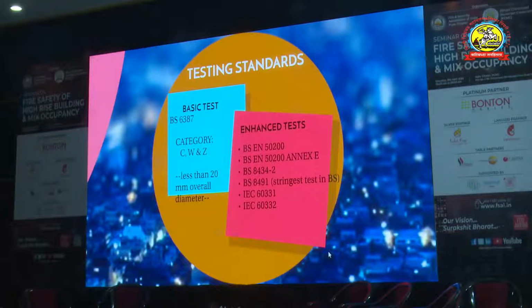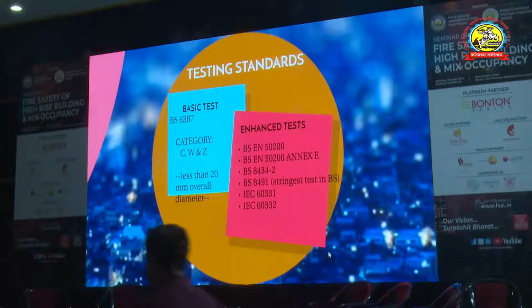Now it states that BS 6387, the basic fire survival test for 950 degrees Celsius over 3 hours, is redundant for anything with an overall diameter of more than 20mm. Cables larger than 20mm diameter must go with enhanced testing, while anything less than 20mm can use basic testing. This is a very important change people are unaware of, so they often ask for BS 6387 in larger sizes, which is technically not applicable.